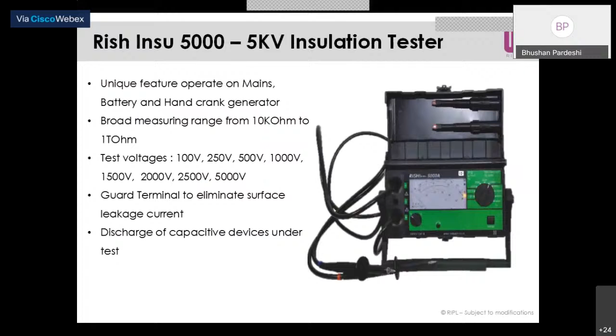It also comes with a guard terminal to eliminate the surface leakage current of any object like motors, reactors, or transformers. It also has a discharge of the capacitive device under test, which means after finishing the test, it will automatically discharge whatever charge is present in the object. It will auto discharge the charge, and it will come into the idle condition.